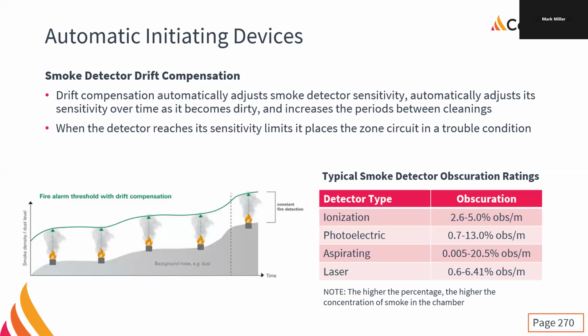With our conventional systems, when it hits the sensitivity limits, it might place the zone circuit into a trouble condition. It does. They don't always. Depends on the specific device, specific manufacturer. Often we just get false alarms. So that's one of the reasons that we have to do our annual testing to make sure that they are working within the proper thresholds. And if you notice that it's getting dirty, clean it or replace it before it becomes an issue. Because there are limitations. They can only do so much.